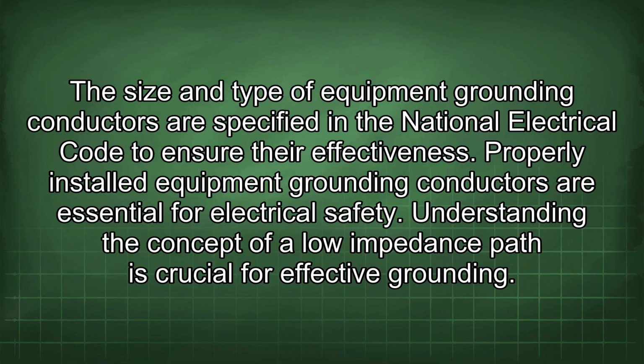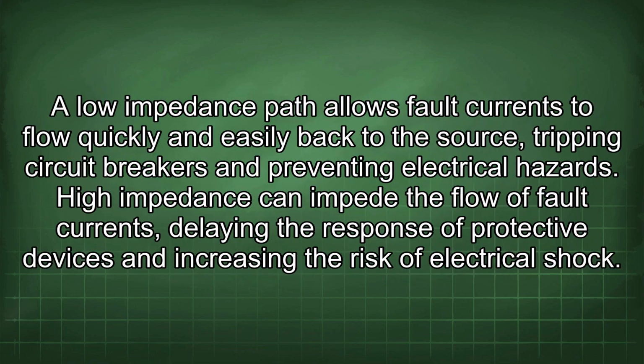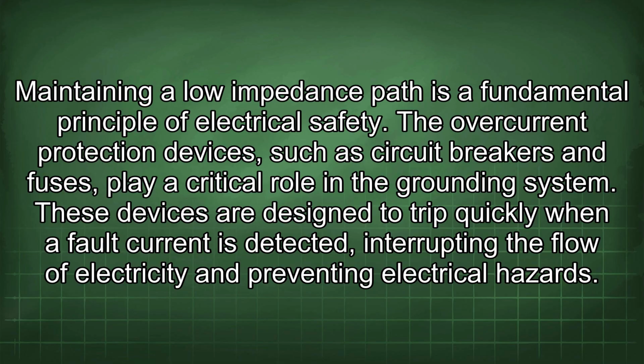Understanding the concept of a low impedance path is crucial for effective grounding. A low impedance path allows fault currents to flow quickly and easily back to the source, tripping circuit breakers and preventing electrical hazards. High impedance can impede the flow of fault currents, delaying the response of protective devices and increasing the risk of electrical shock. Maintaining a low impedance path is a fundamental principle of electrical safety.